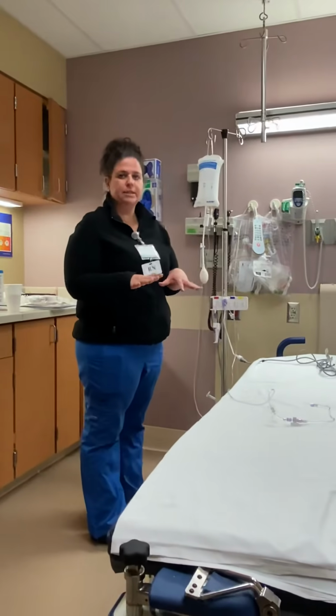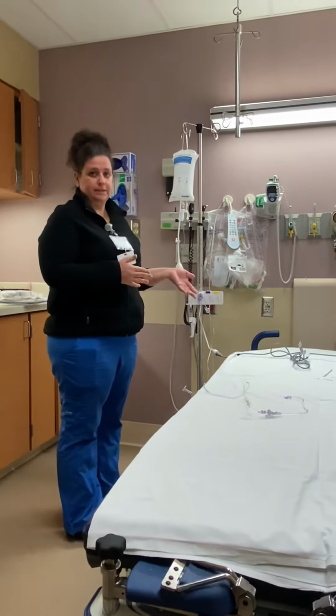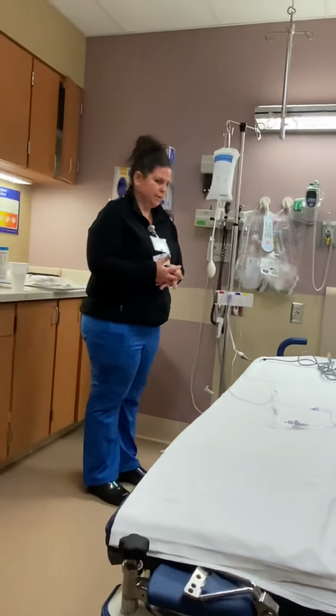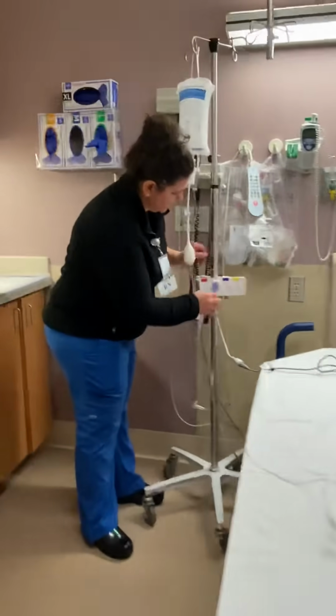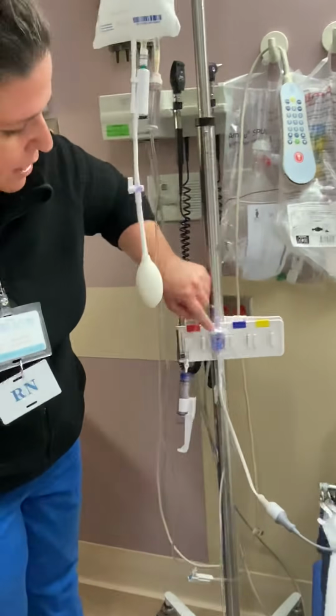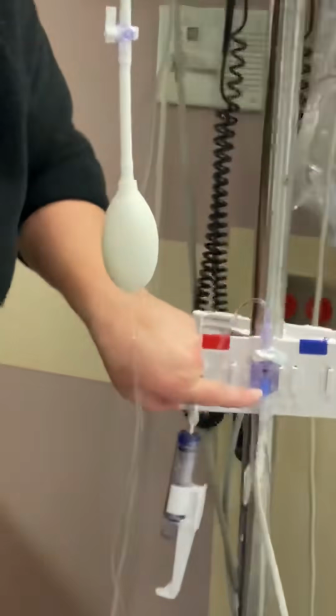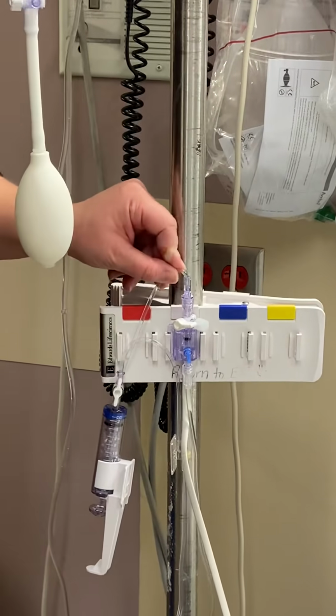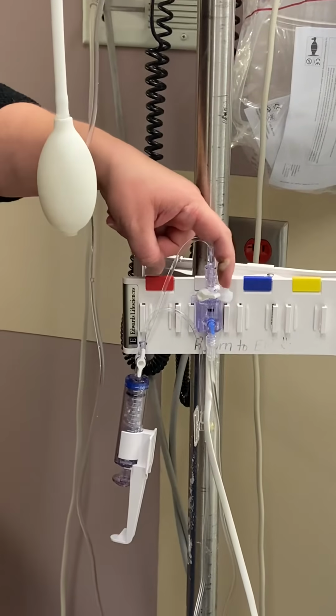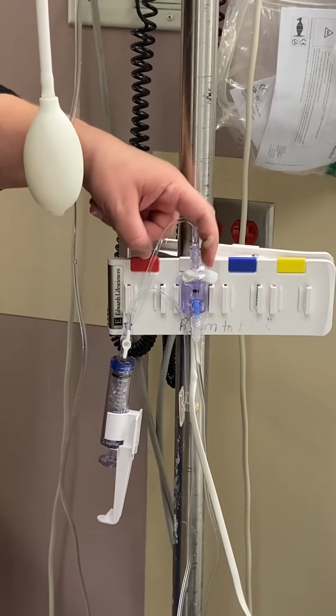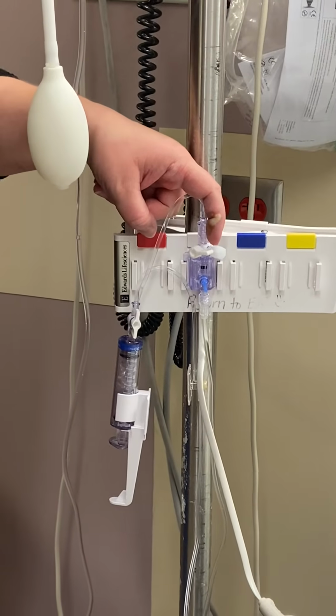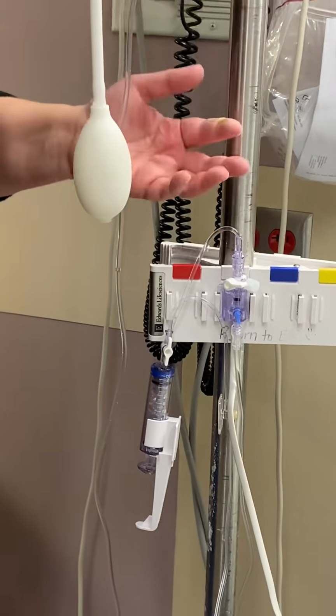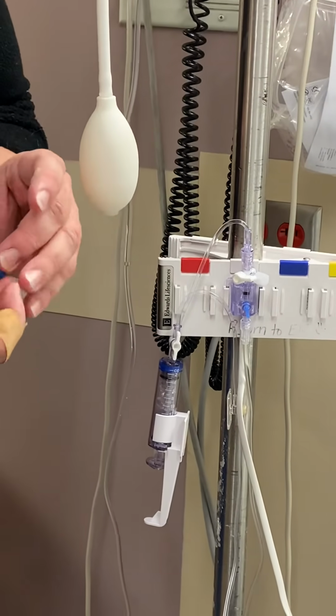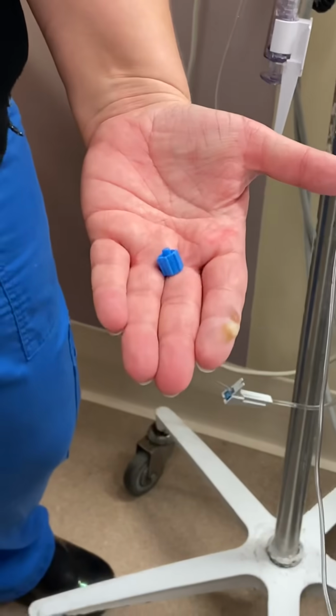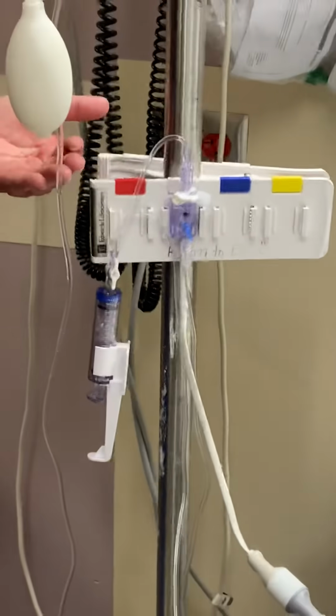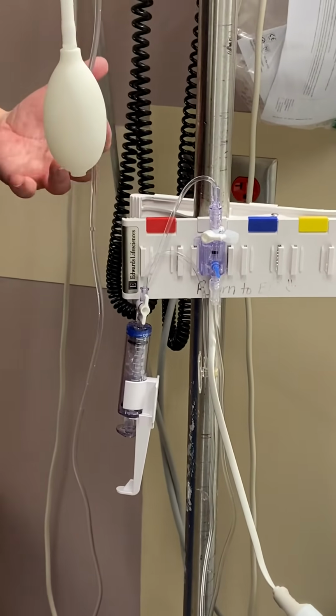Once we've gotten this connected to the patient, I need to then zero my system, okay? So here's how we do that. If you look here, you're going to see that you have your valve, and then you have your 0 port, and you have your pigtail. When I take this out of the package, I have a white valve on my 0 port. This is a vented valve. I need to remove this in order to use the system and replace it with a non-vented cap. So in your package, you're going to have the blue non-vented cap. And so while I'm zeroing my system, I'm just going to go ahead and replace the cap during this time.